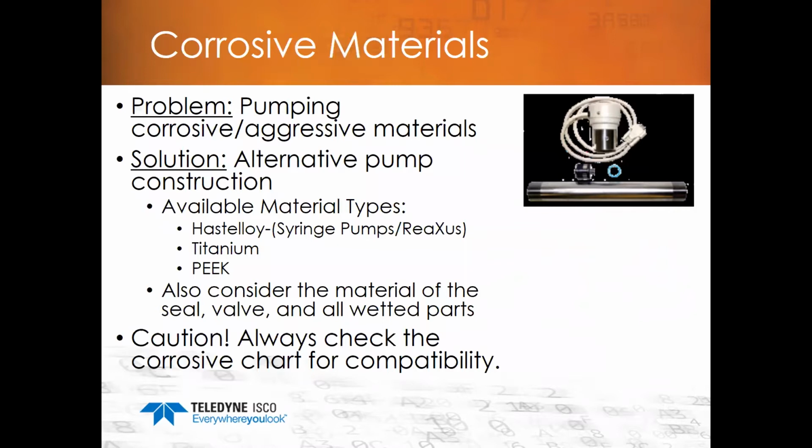You can get ahead of the curve by doing that, because you'll be able to express or detail out to the customer, this is what you need. Or they'll tell you, and you go back and look at it in detail with the factory that you're buying it from, this is what I need. So corrosive materials is a consideration and can be a tougher application because some materials are much more aggressive than others, especially to certain types of pump materials or flow path materials, okay?